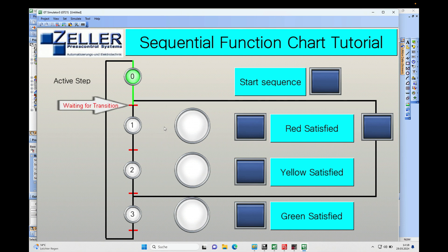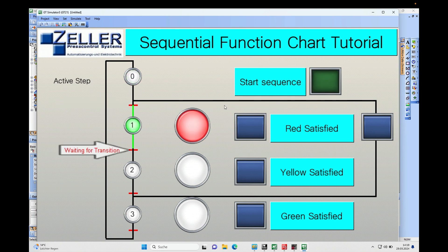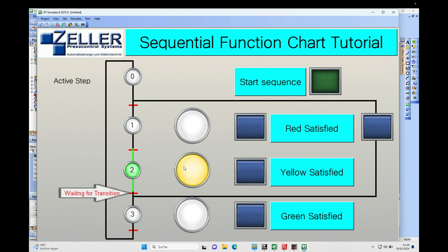In this example you will see the SFC program is already active. In order to start it and set the first step, I'm going to start the sequence. We will see it switches over to the next step — step number one, which is the red light on — and now it is waiting to satisfy the next transition following that step. I created a button right here which satisfies the condition. If I push that, it switches over to the next step and the previous step switches off.